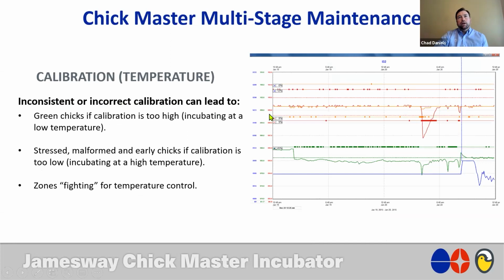If you are lucky enough to have Maestro, where you can look at front zone and rear zone cooling, front zone and rear zone heating, and you recognize huge differences such as this over a day, 24 hours, we saw that the front cooling worked 12% of the time and the rear cooling didn't work, but just there's one little spot right there. So this tells us that this machine is using a lot of front cooling and no rear cooling.